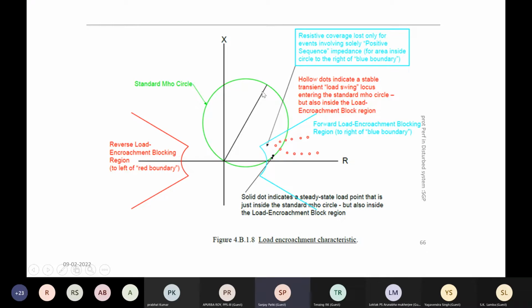Now, in this case, the relay is not able to distinguish between the load causing encroachment into the impedance characteristic or whether it's a three-phase fault. Because as far as the relay is concerned, relay sees it as a three-phase fault. This is the load swing. Now, during the 2012 grid collapse, some of the distance relay protection did not have this load encroachment prevention feature. So a number of lines tripped on this load encroachment, giving the indication of a zone 3 three-phase fault.